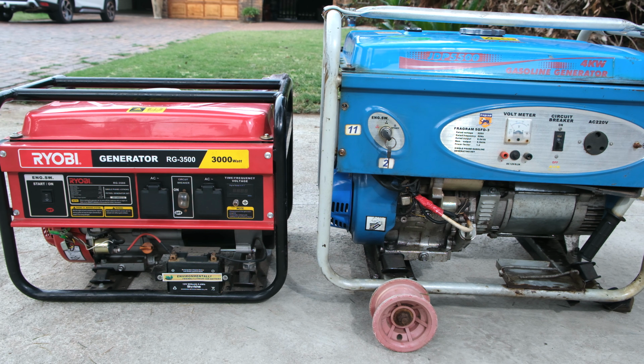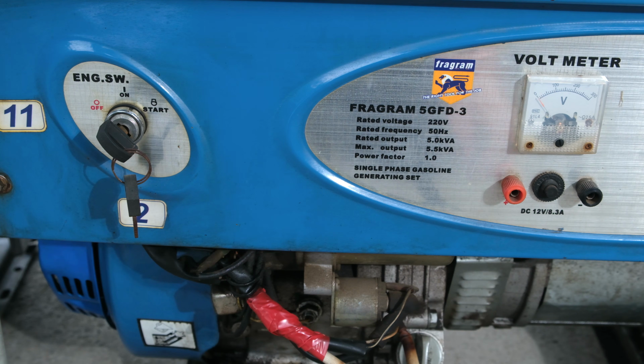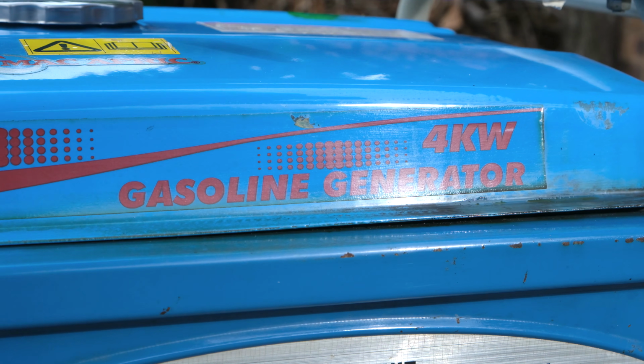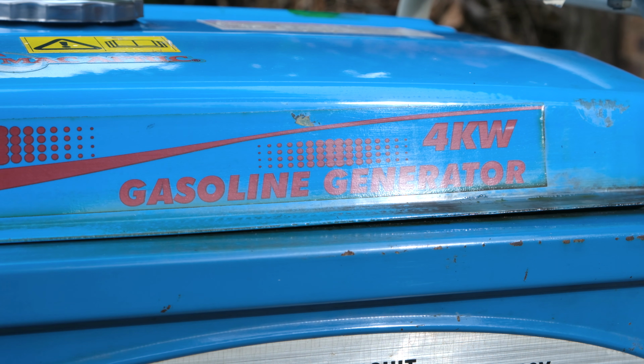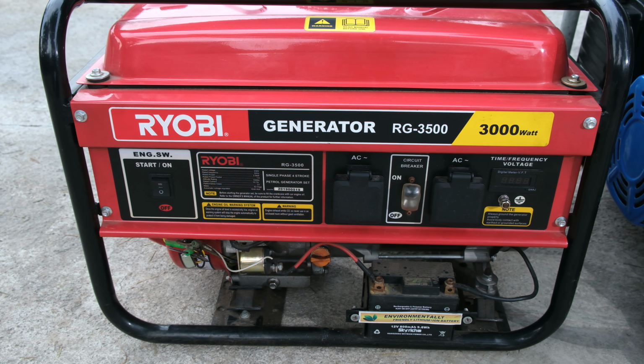When using your generator, do not run it at more than 75% of its rated maximum wattage. For example, this says 5 kVA. But actually it's a 4 kilowatt generator, which means I should not connect more than 3 kilowatts to this generator. In the case of the smaller generator, it's rated at 3000 watts. Do not exceed a load of more than 2.2 kilowatts for this smaller generator.